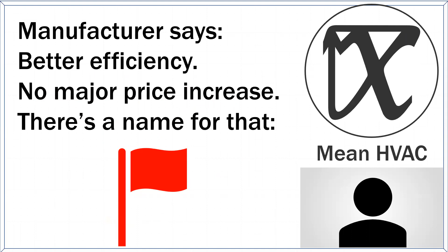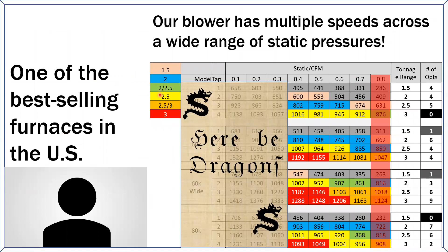This color code is how many useful speeds there are to get the amount of airflow you need at 1.5, 2, in between, 2.5, 3, and in between. Because this blower is in one of the most commonly sold families of furnaces on the face of the planet. There are actually 1, 2, 3, 4 different furnaces that you can get that use a 3-ton drive. And they use that 3-ton drive for 1.5, 2, 2.5, 3, right? They use it for all of those sizes.